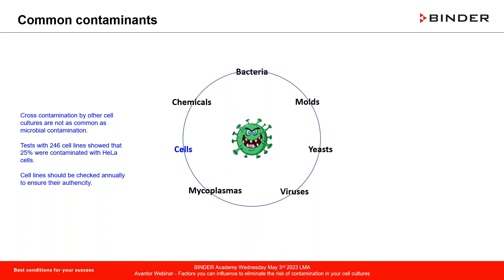Then chemical contamination. I'm not quite sure if you are aware of these things. You have plasticizers. If you come into a new building, a lot of plasticizers are in the air from your furniture, from the ceiling material, from adhesives, and that might have a detrimental effect because those airborne chemicals find their way into the CO2 incubator. That makes it very difficult to detect because the first idea you have is some kind of microbe. Residuals: if you're conducting a wipe disinfection and you're not cleaning it properly, if you're not wiping it down thoroughly, then you have a risk, as well as with VOCs, volatile organic compounds coming from the environment.